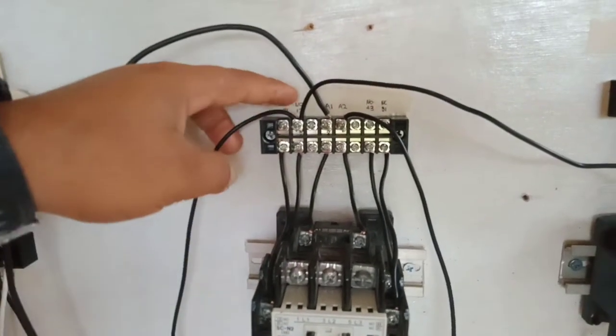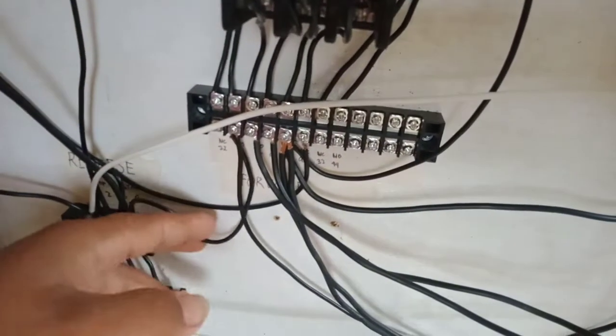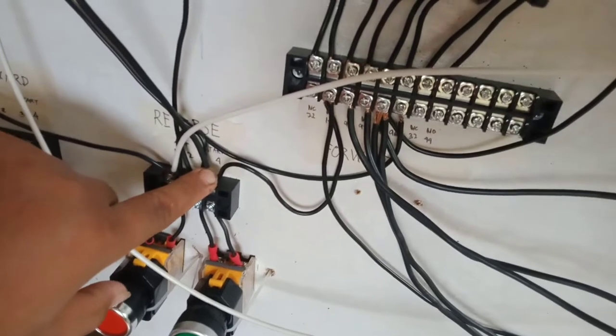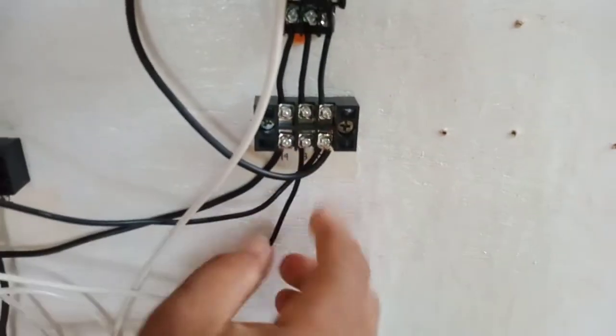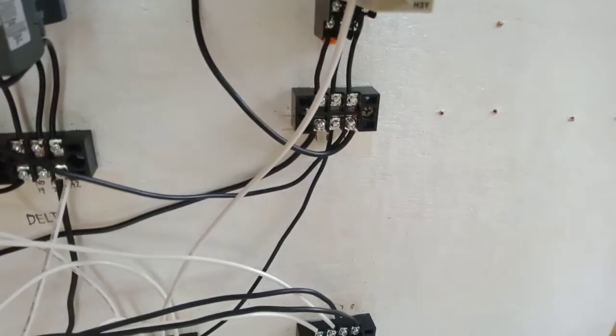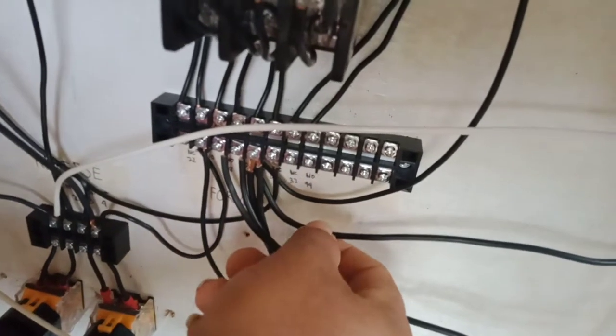Stop three going to main contactor number 13, and main contactor number 14 going to start four. Main conductor number 14 also going to timer terminal 13. Timer terminal 14 going to overload relay terminal 95, and main contactor number 13 going to timer terminal 9.